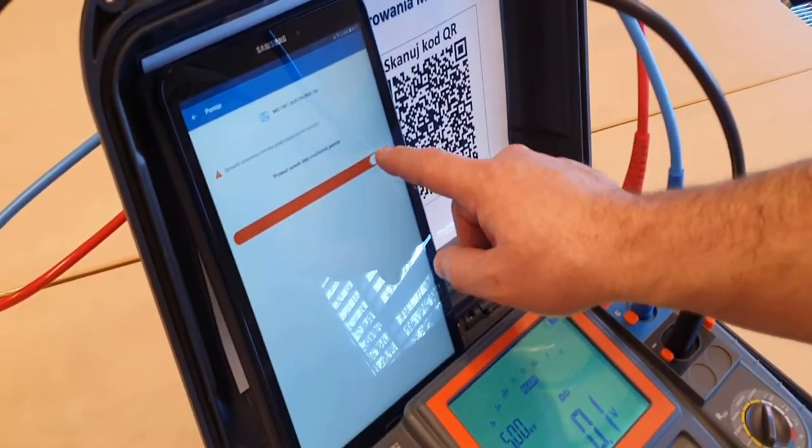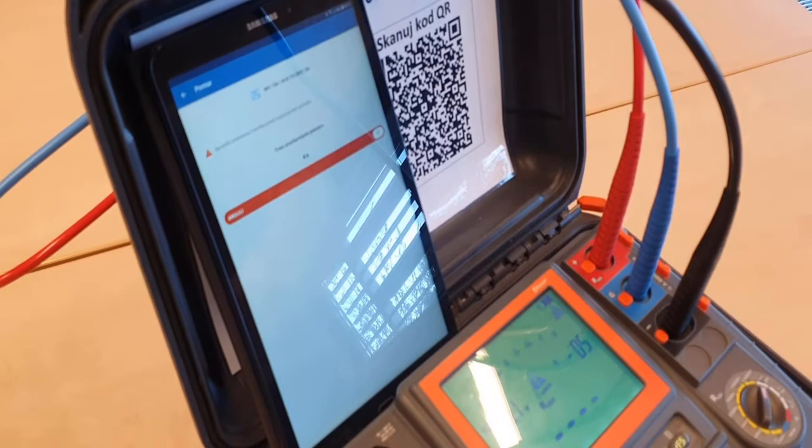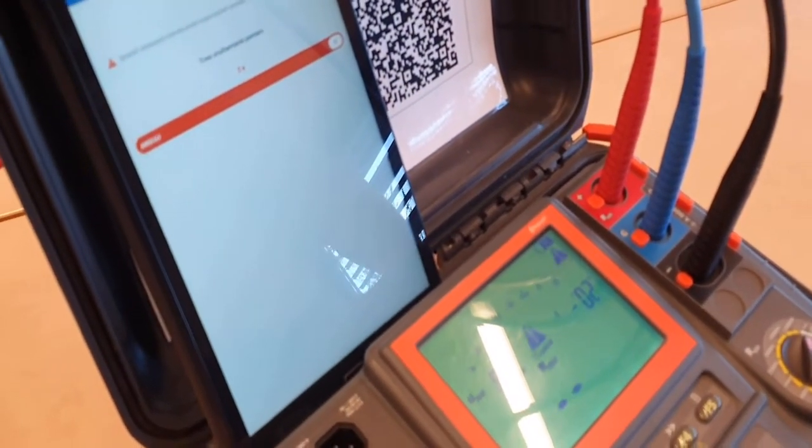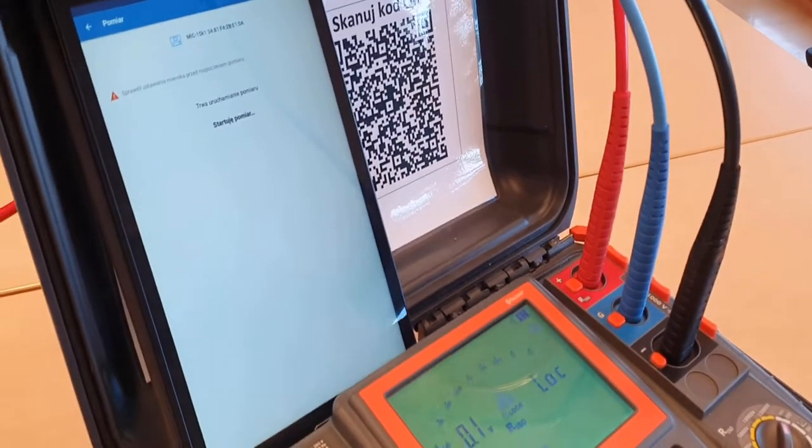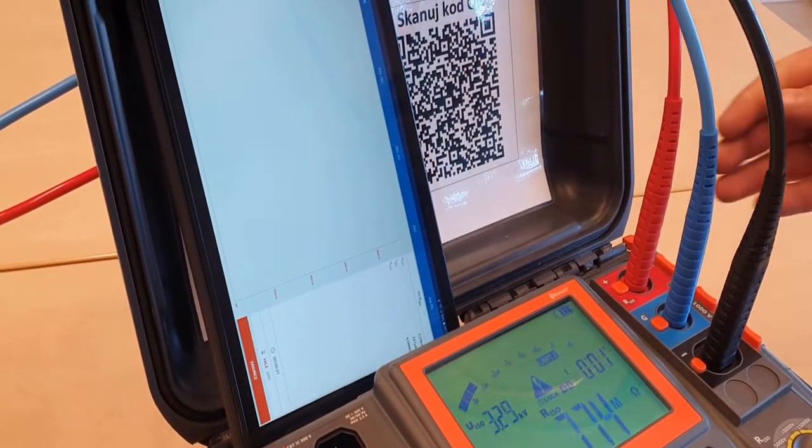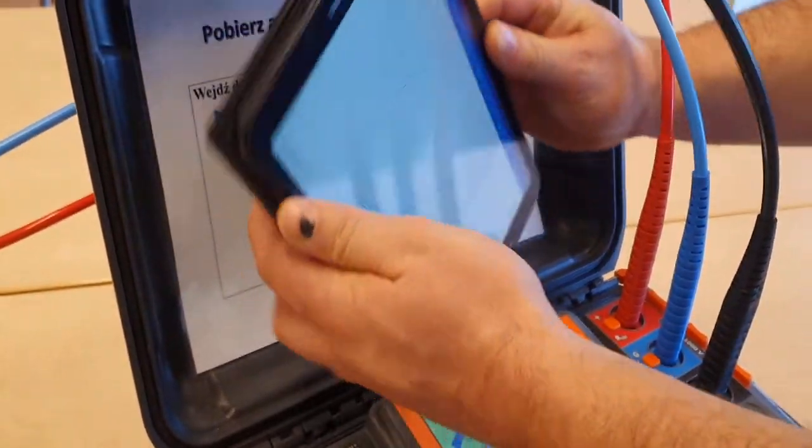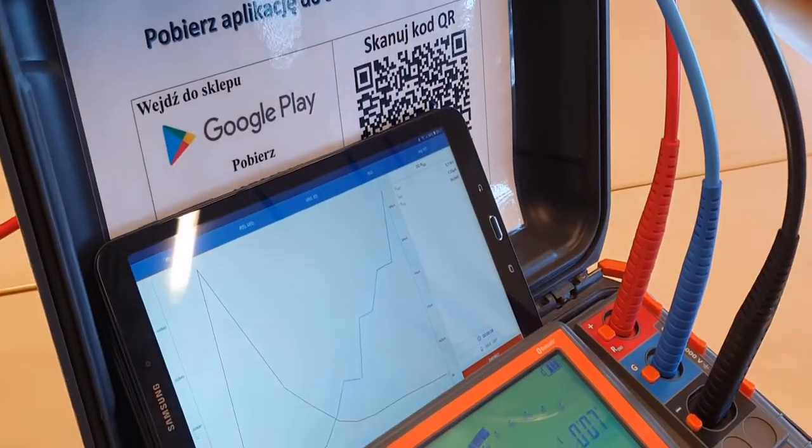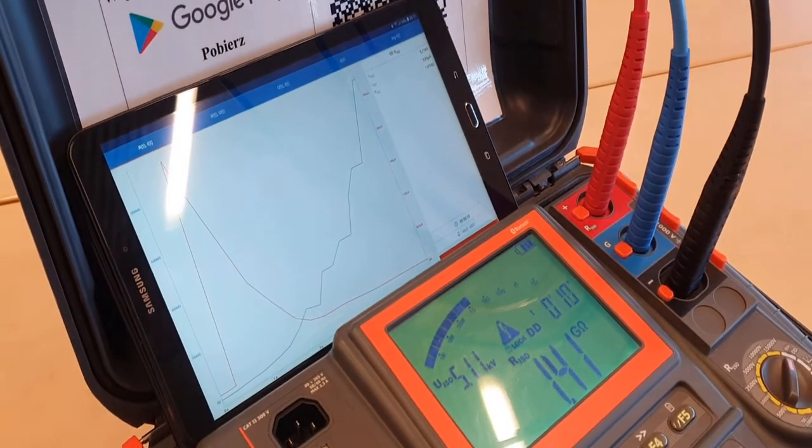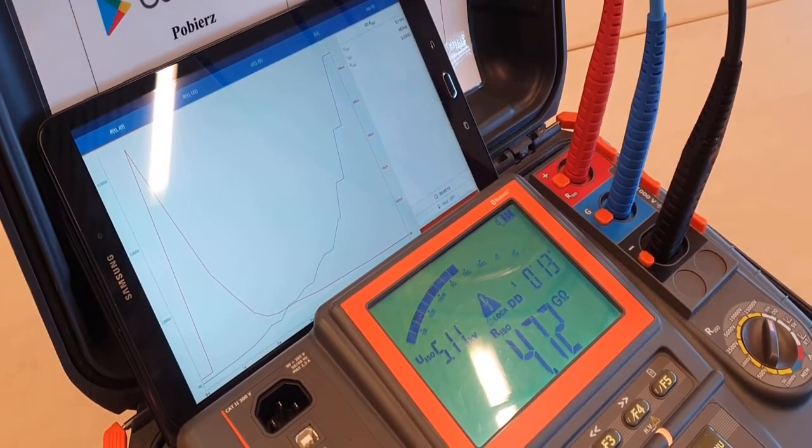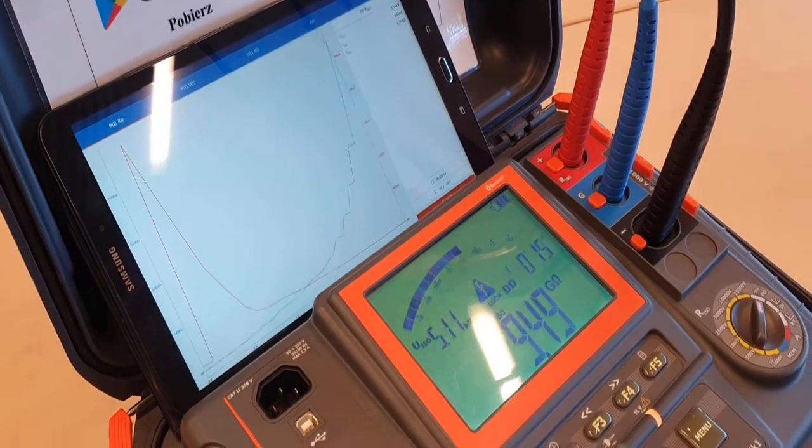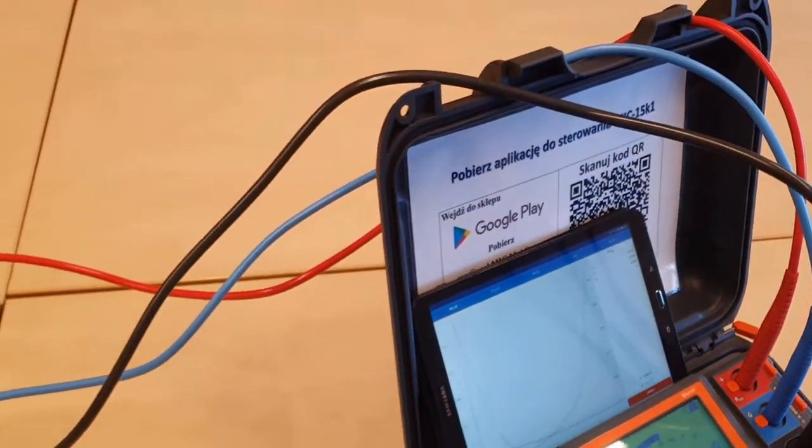For safety reason, to start the measurement, you have to drag the slider on the screen. In addition, the meter will count down 5 seconds before applying the voltage to the object. Now the object is polarized. The charging time is 5 minutes. And then it will be discharged and the depolarization currents will be measured, also 5 minutes. The screen shows graph of current and resistance over time.